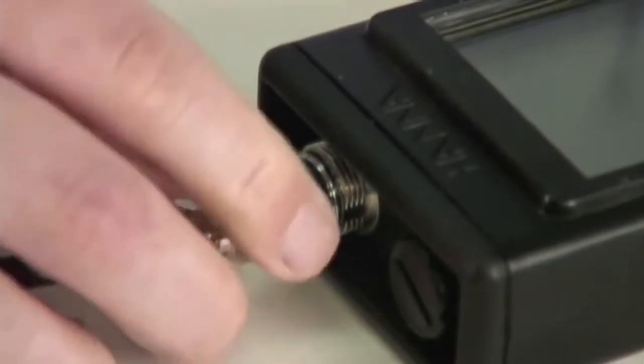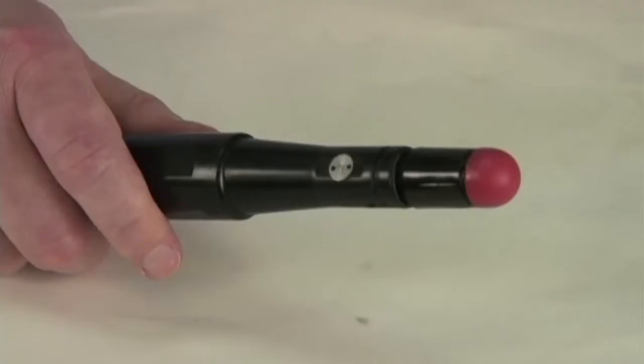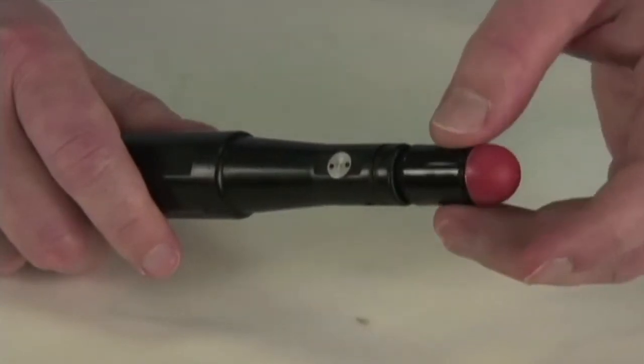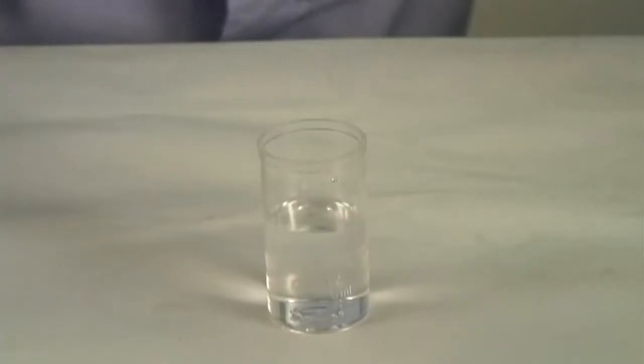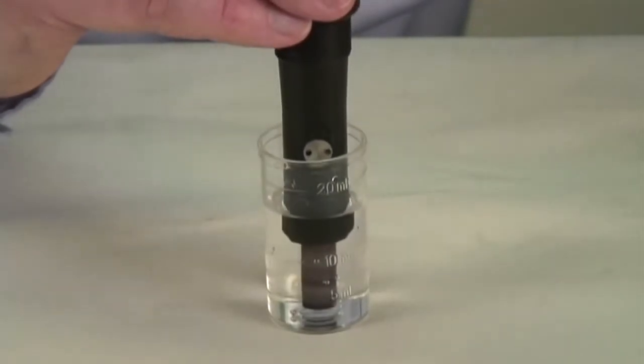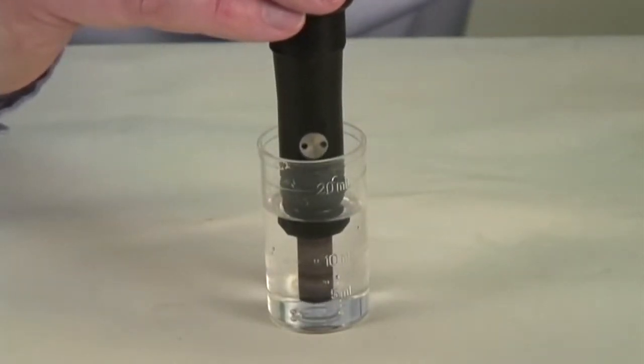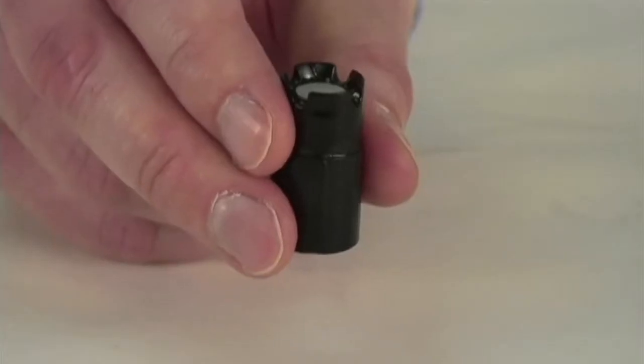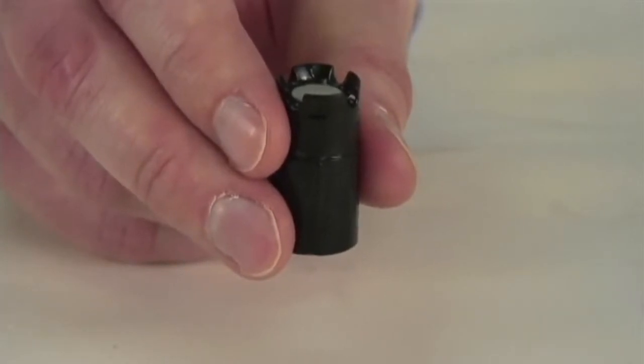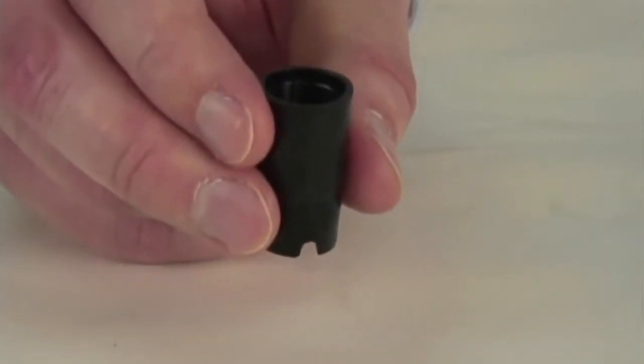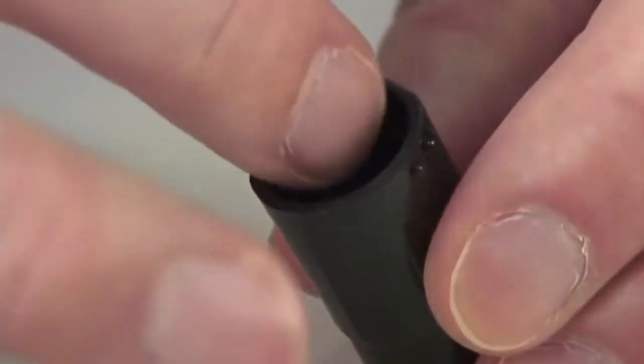Step 1. Connect the probe to the meter. Be sure to align the pins with the socket and tighten the threaded ring. Step 2. Remove the red and black plastic cap from the probe. That's just for shipping. Step 3. Prep the sensor by soaking the bottom inch of the probe in electrolyte solution for 5 minutes. Step 4. Inspect the membrane cap. Make sure the membrane isn't damaged and that the rubber O-ring is seated properly inside.